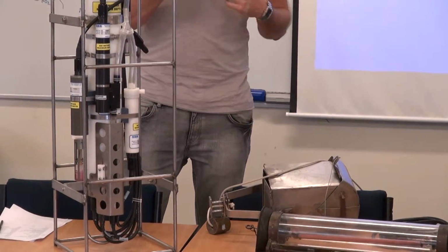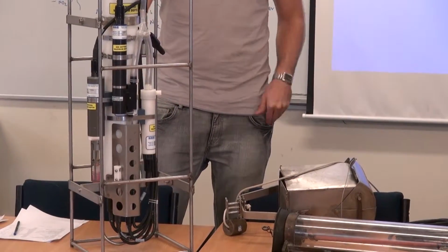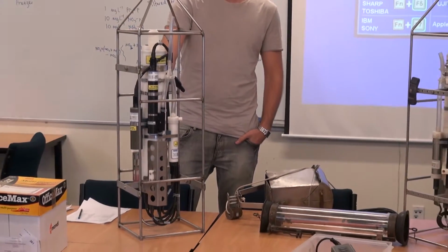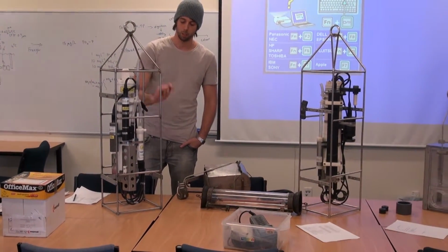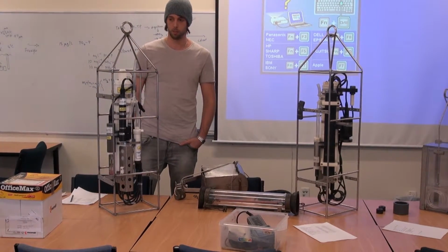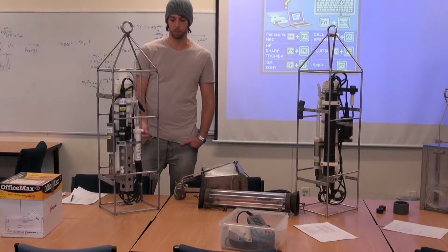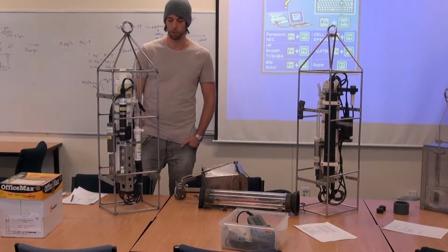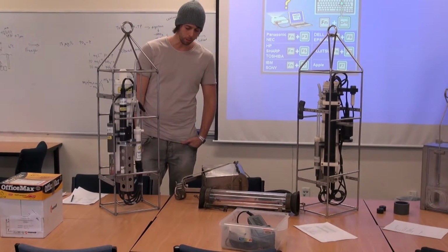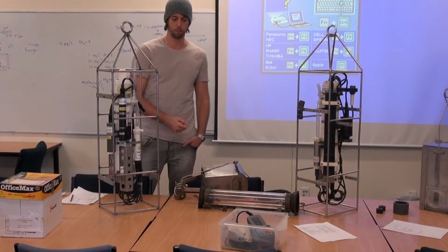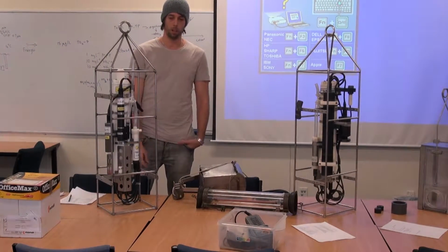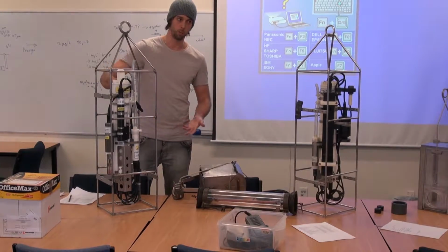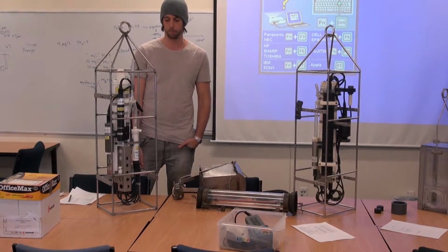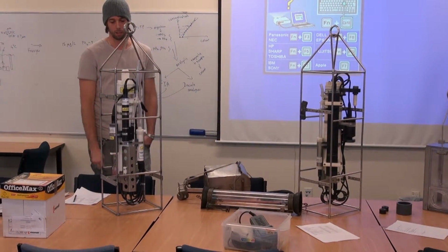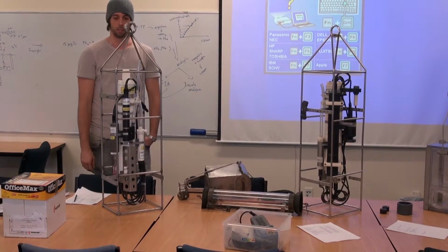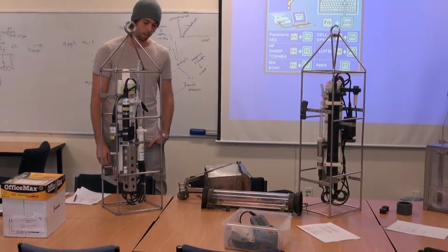So what happens is you lower it over the side of the boat into the water, and there's a set amount of delay, and we always keep that delay at 60 seconds. So the conductivity sensor will pick up a reading that's high enough to flick that pump switch. The instrument will wait for 60 seconds, and it'll turn on, start cycling the water through, and then you're good to go. So the procedure we use is turn it on, hold it over the side of the boat at the surface, fully submerged but not deep, for 90 seconds at least. It's always a good idea to time that rather than guess it, because a minute can seem like a long time when you're waiting for it to happen.